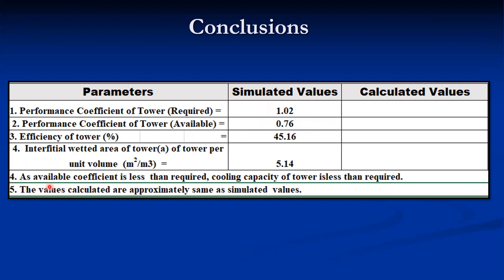The conclusion is: since the available coefficient (0.76) is less than the required value (1.02), the cooling capacity of the tower is less than expected. The interfacial wetted area of the tower per unit volume is 5.14 m²/m³. These are simulated values. A simulator is provided — by inputting all the conditions, the simulator calculates all these values. You have to perform the calculations manually and validate your results with the help of the simulator.